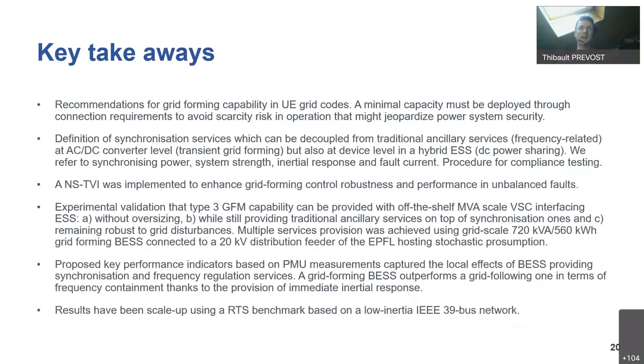Key takeaway, if I want to go very fast through that: I think it was a negative sequence TVI, because it was made to work on a real system where the voltage is not balanced. Here we have demonstrated also that the type 3, as we said, grid forming capability can be delivered by an MVA scale inverter that was just an off the shelf one. And we have also indicators that are based on PMU measurements that can capture the effect of this battery energy storage system and discriminate between what we would like to have, grid forming, and grid following ones.